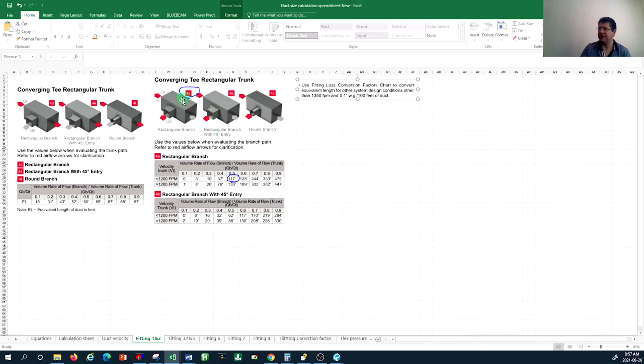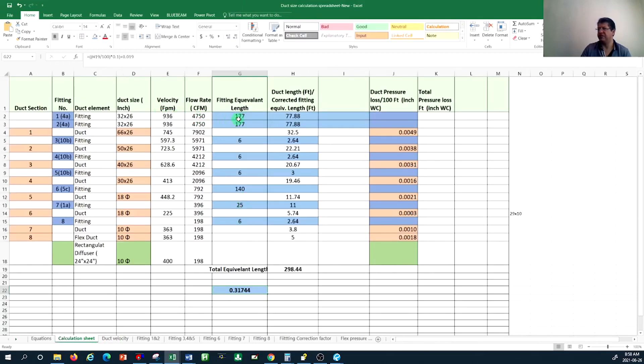I look at type 4A for the branch path and the trunk side. The number from those tables is 60 for the trunk and 117 for the branch, giving a total equivalent length of 177. When we say total equivalent length, this is the equal friction pressure drop for that specific fitting. At 1,000 feet per minute with 0.1 inch water column per 100 feet, 177 feet equivalent length multiplied by 0.1 divided by 100 gives 0.177 inches of pressure drop across that fitting alone.